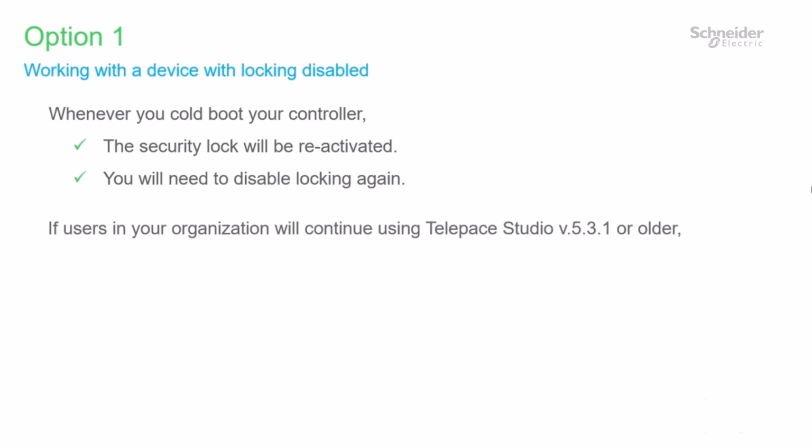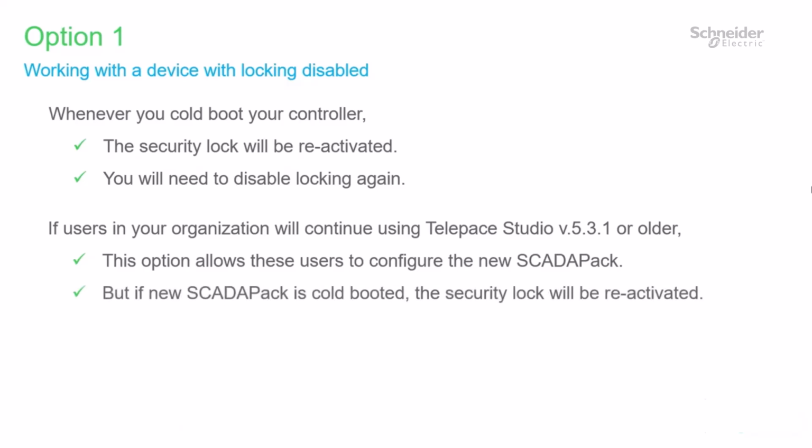If you have users in your organization that intend to remain using Telepace Studio 5.3.1 or older, then disabling the security lock allows these users to configure the RTU without issue. However, if one of these users needs to cold boot the controller, the security lock will be reactivated, and only Telepace Studio 5.4.1 or newer can disable locking at this point. All the more reason to have all users update their PCs with the latest version of Telepace Studio.